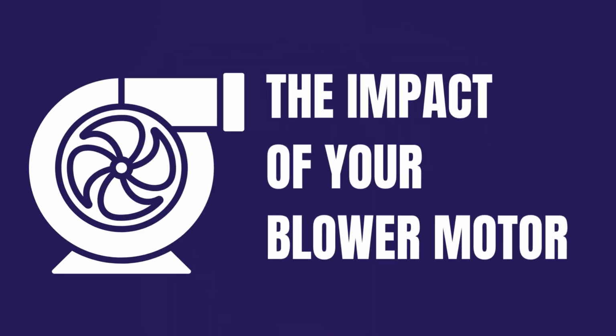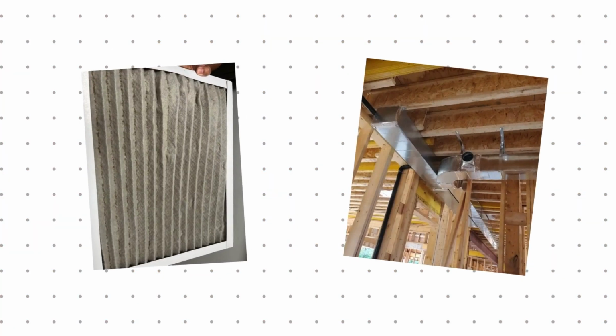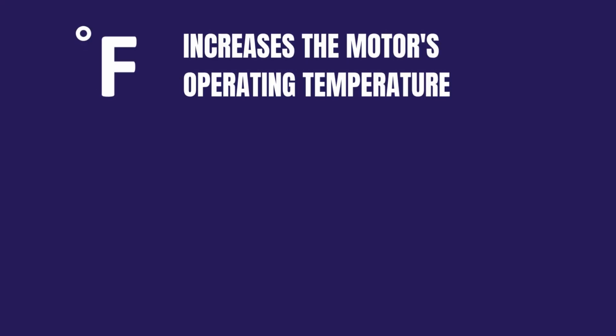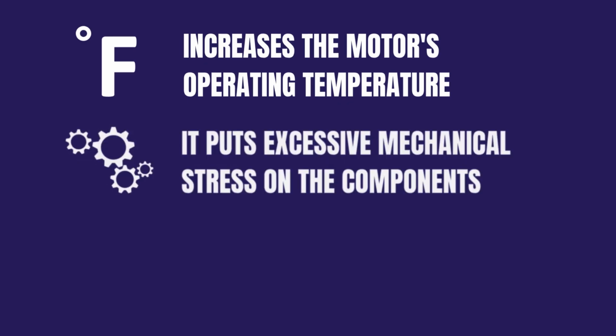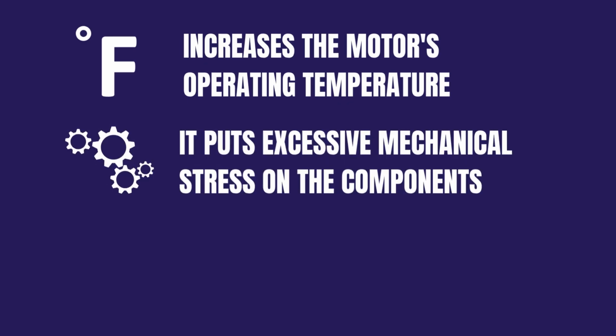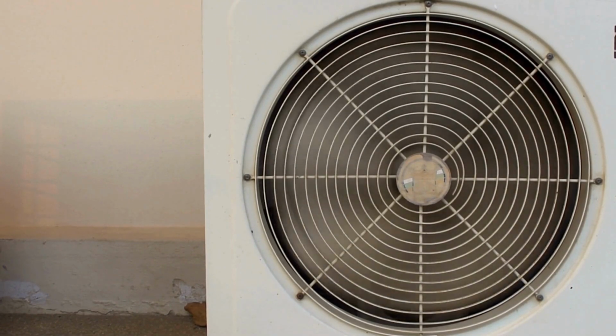The impact on your blower motor. One of the first victims of poor static pressure is your blower motor. When static pressure is too high, usually from dirty filters or undersized ductwork, it forces this motor to work much harder than it should just to move the air. It's like trying to blow air through a straw versus a paper towel tube. One requires much less effort than the other. This extra strain does 3 damaging things. First, it increases the motor's operating temperature. Secondly, it puts excessive mechanical stress on the components. And lastly, it dramatically shortens the motor's lifespan. And I've seen blower motors fail in as little as 2 years when running under high static pressure conditions. Motors that should have been lasting 10 to 15 years with proper maintenance.